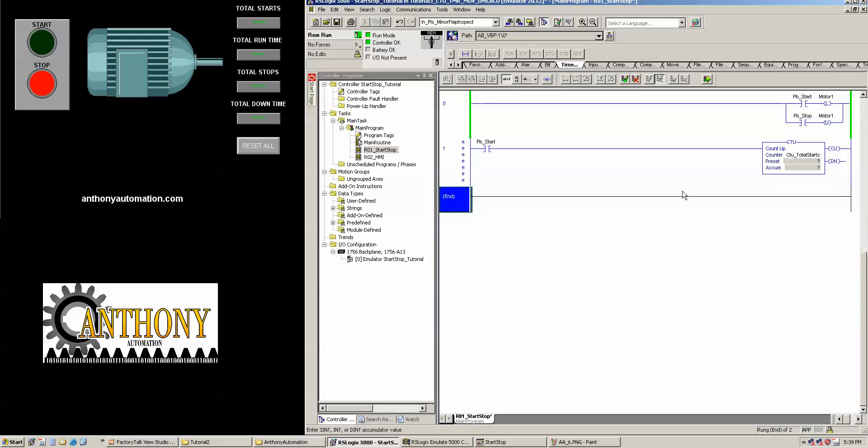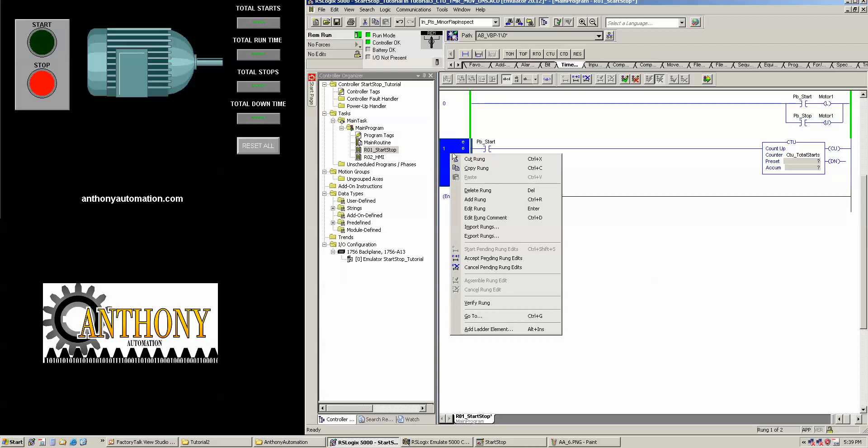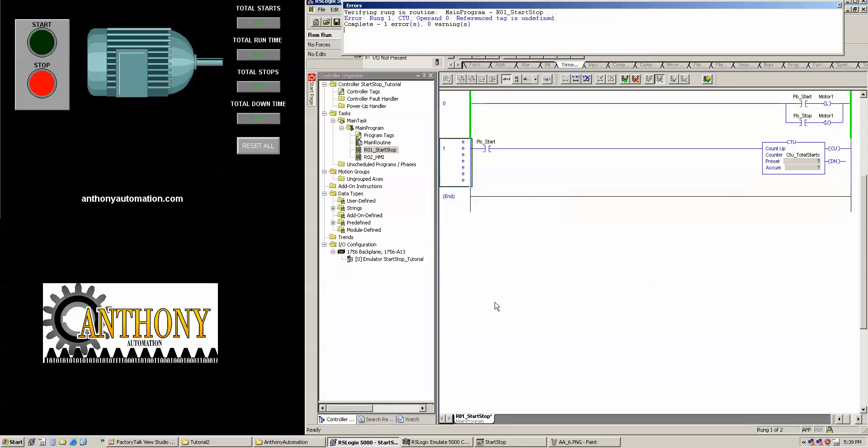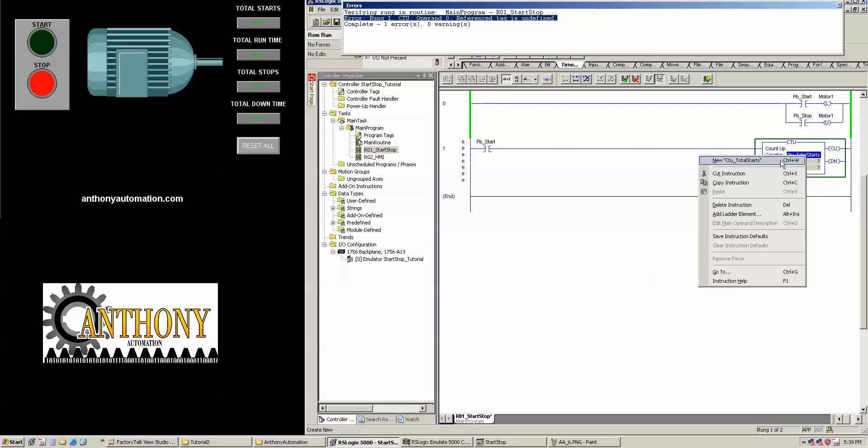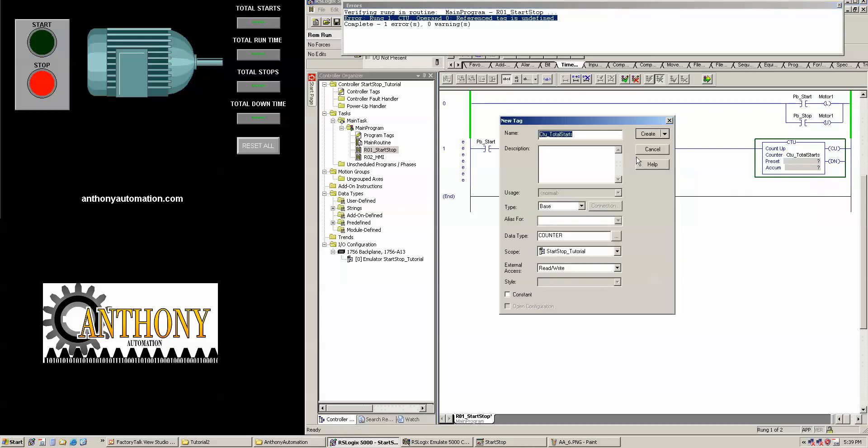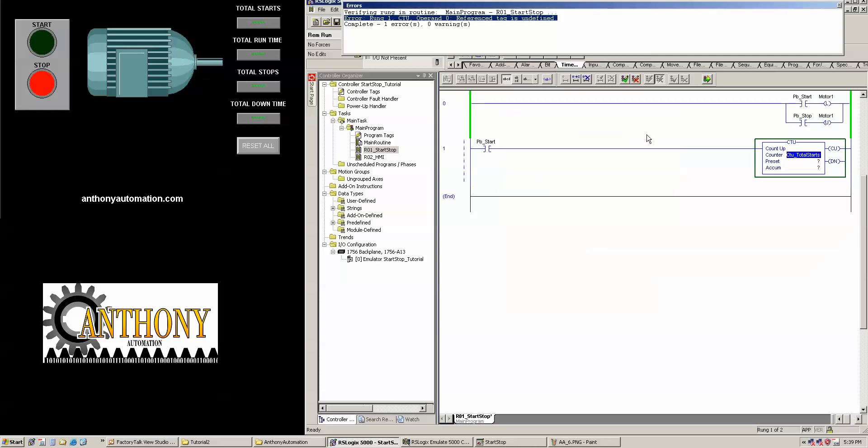Then, it still doesn't know what's going on. These E's mean that there's a problem on that rung. Now, you can right-click on here and say verify rung, and up here it'll tell you exactly what's wrong. And you can click on that, and it'll tell me, hey, we don't know what this is. We're going to have to give this guy a name and put him in the global tag. So, it's a base tag, means it's not alias to anything. The type of data type is a counter, and it is a global tag. I want my whole program to be able to see this. So, I'm going to say create that tag.